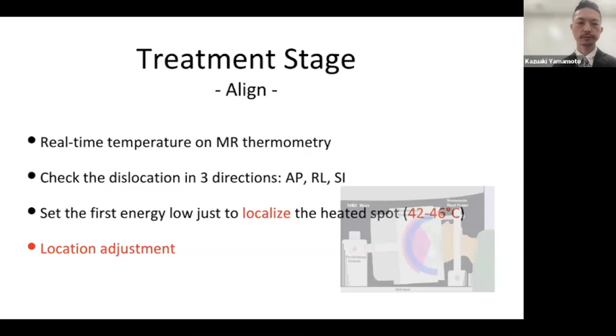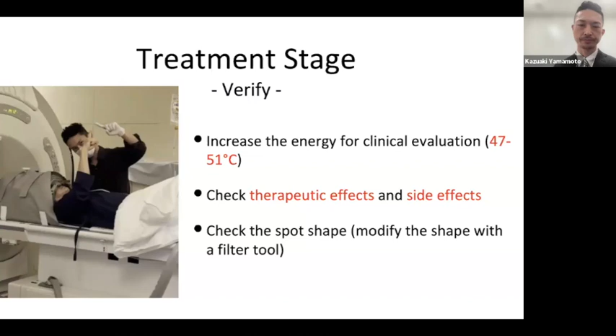And in the verification phase, we can see therapeutic effects and side effects with target temperature around 47 to 51 degrees Celsius. These effects are reversible in the verification phase. We also check the shape of the heated spot. If the shape is distorted, we can modify the shape using a filter tool bundled in the system. Once the location is confirmed and there are good clinical effects and absence of side effects, we can move to the treatment phase.